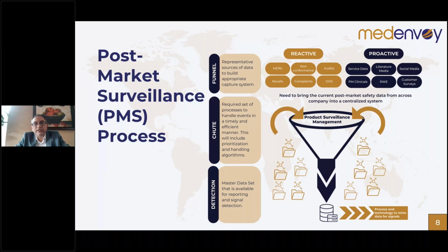Complaints, any vigilance, any non-conformities, any out of specification, any audit findings, something that already has happened to your device. So you're reacting to a situation, an issue. Proactive elements are things that have not happened to your device yet, but you have become aware of.